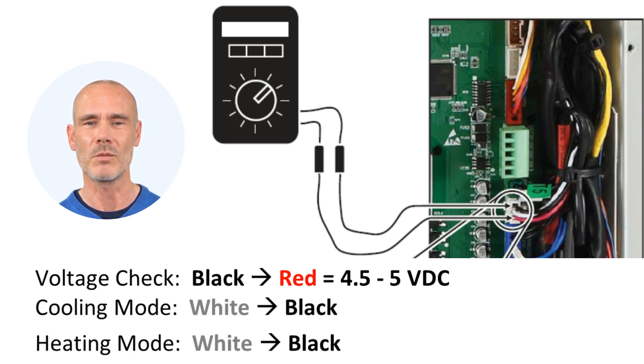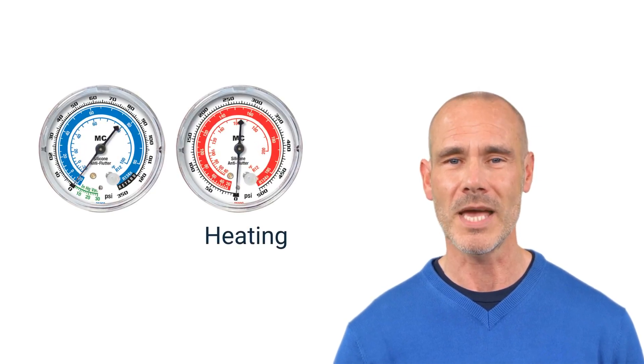Next, read across the white and black wires to get your operational value. You can check the transducer in either heating or cooling. Heating will be tested on the high side and cooling will be tested on the low side.